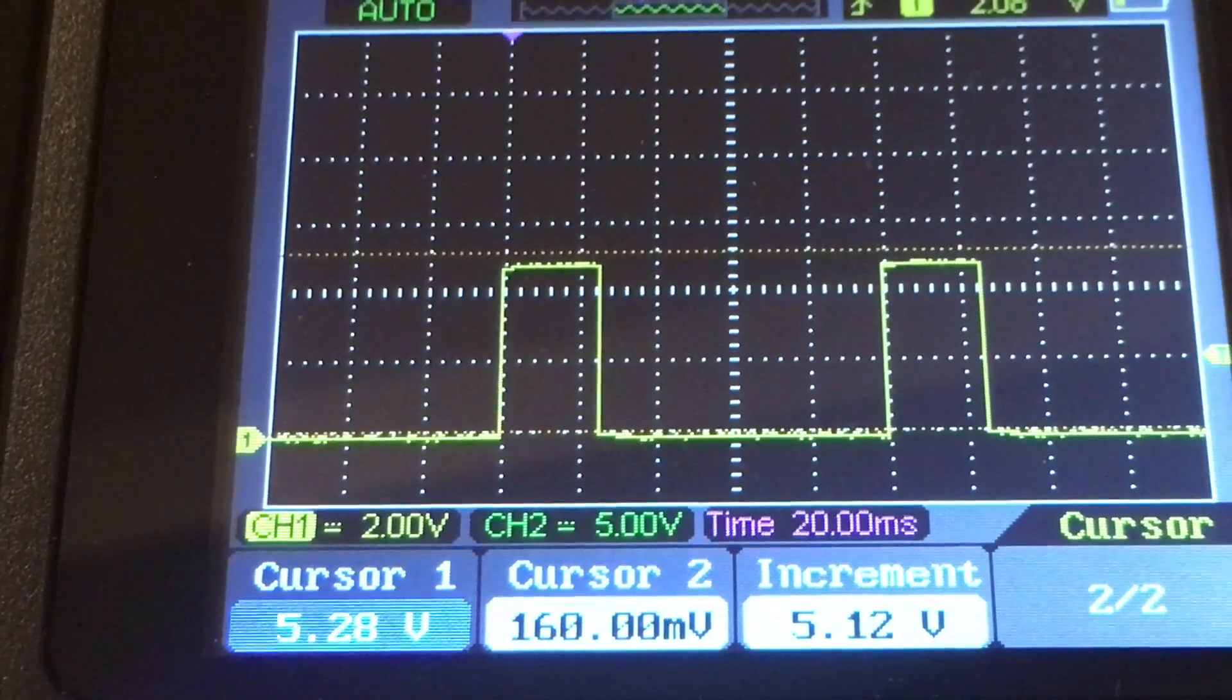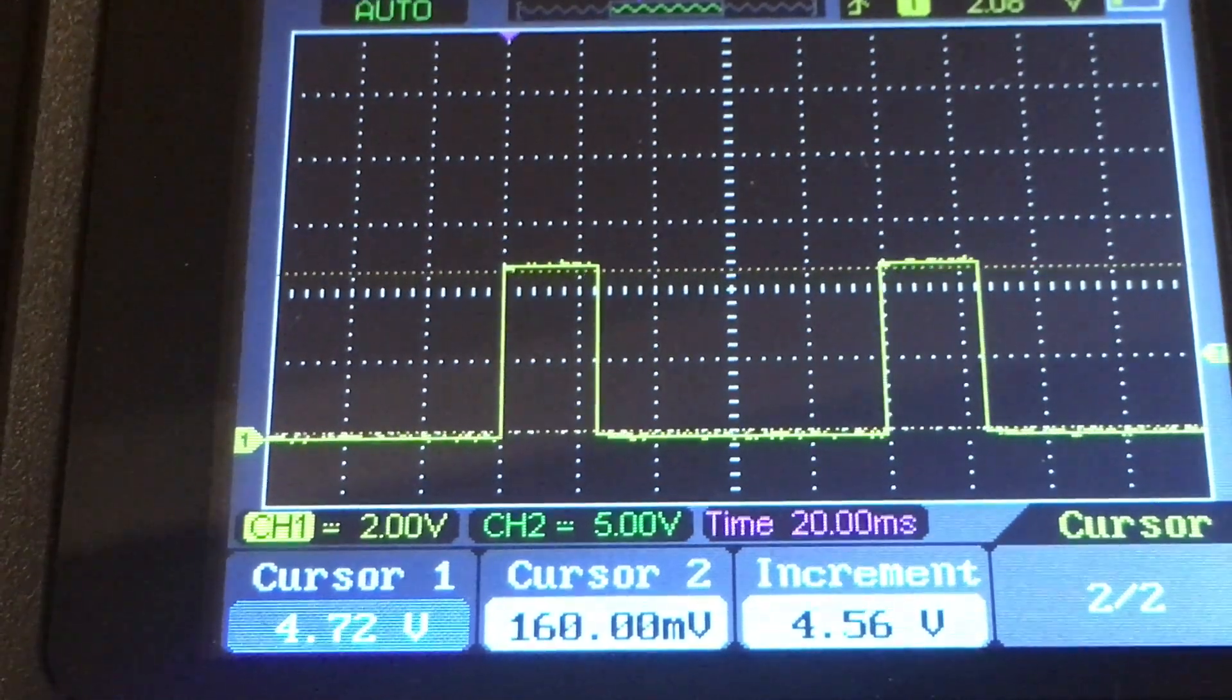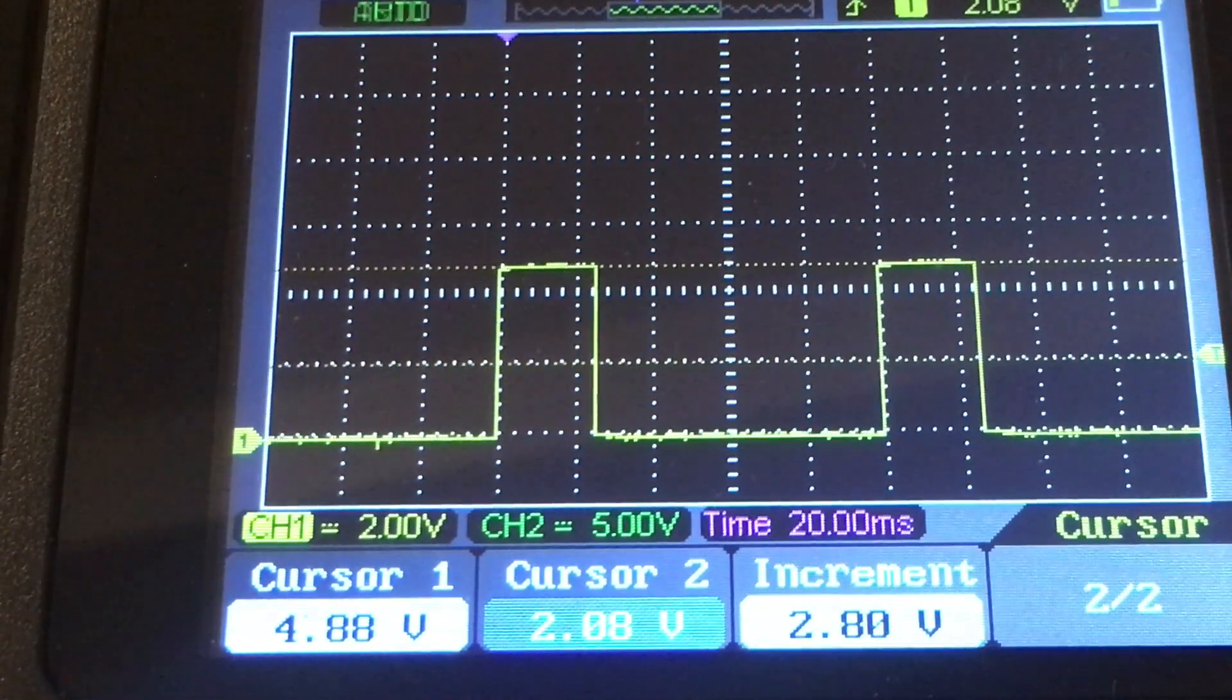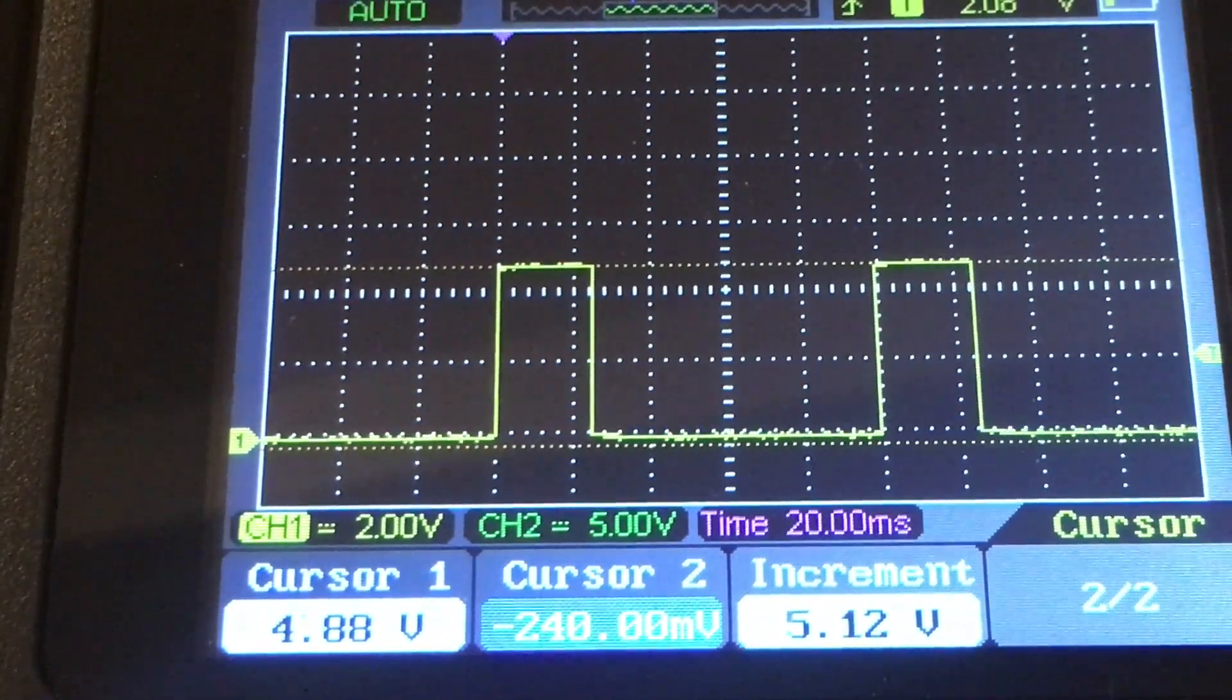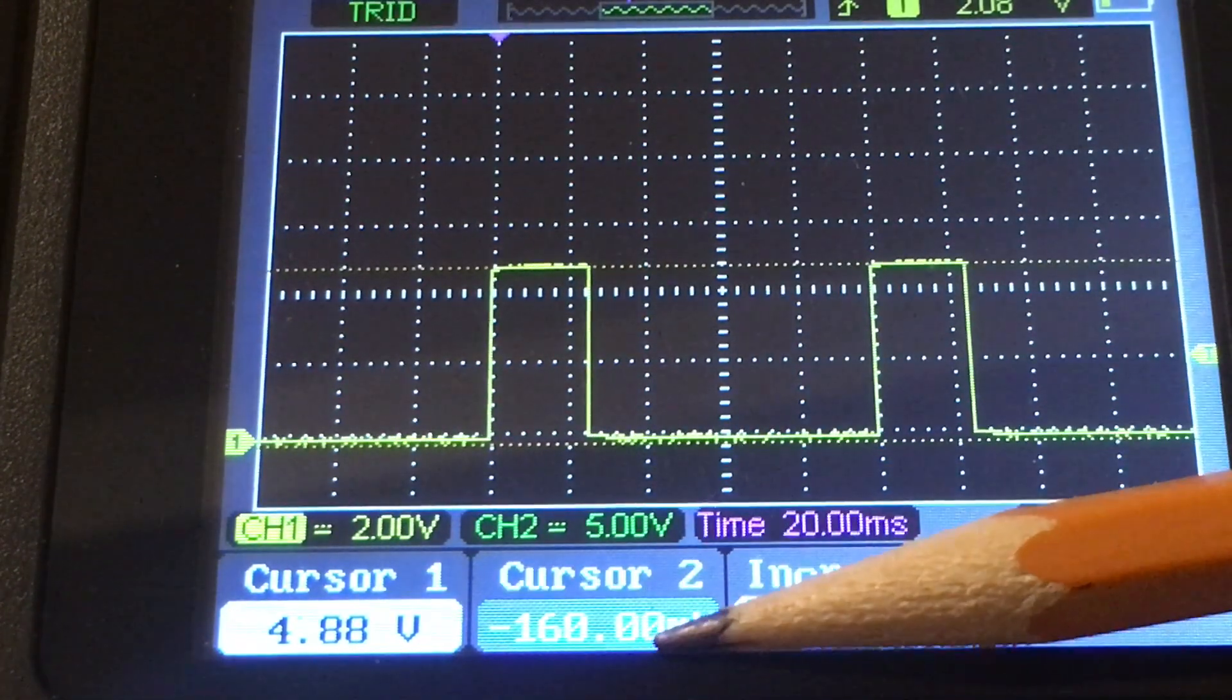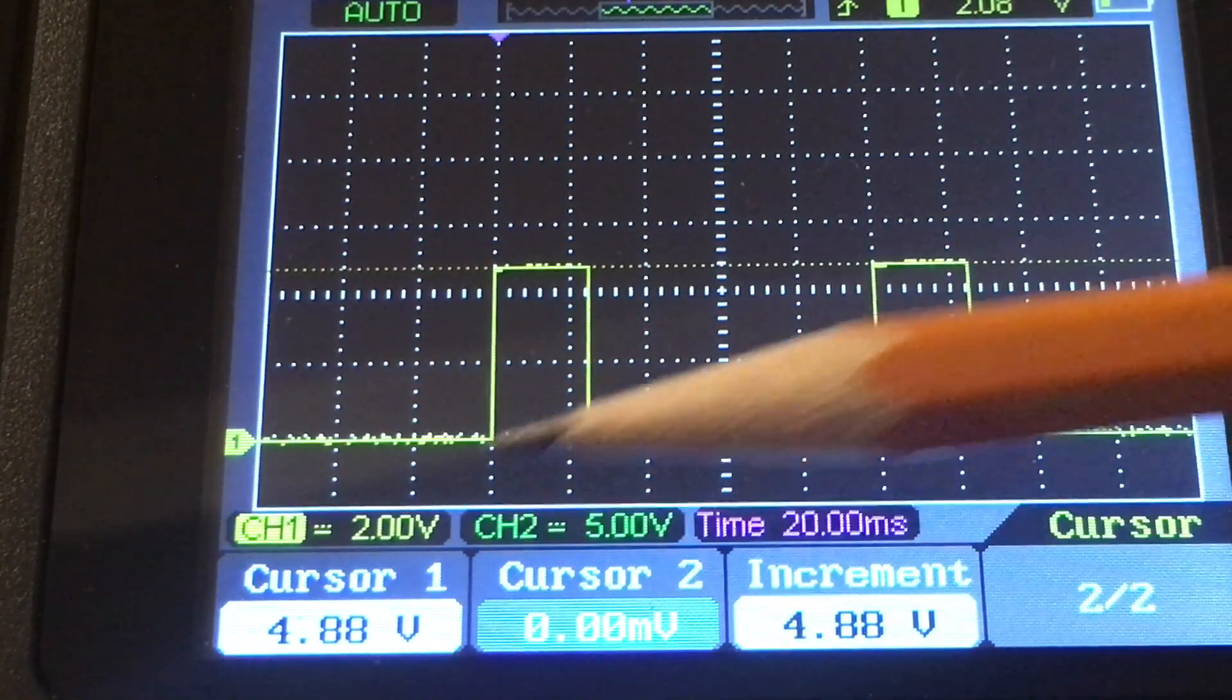It's giving us the value there. You can see the line coming down, cursor one on the far left bottom left display. I can go to cursor two and set that to wherever I want. Basically you're looking at absolute values and differential. That is what the increment is referring to. If you take it off the zero line, you can see that what you have is absolute values where the cursors are and the differential. On the zero line, those two are going to read the same. That makes sense.